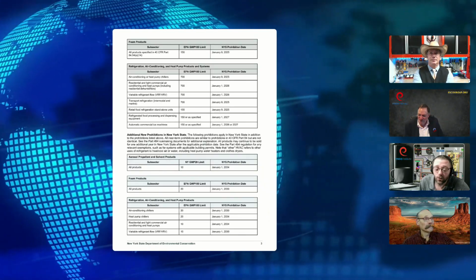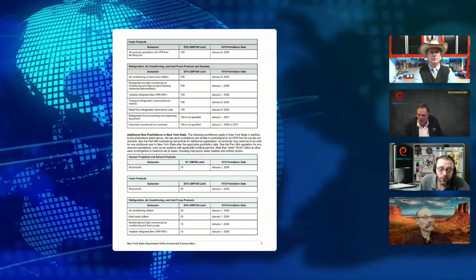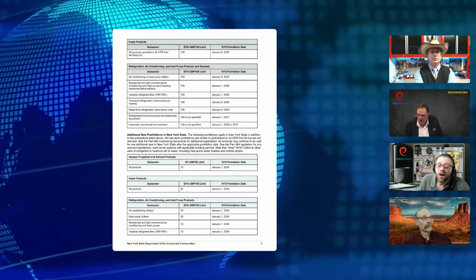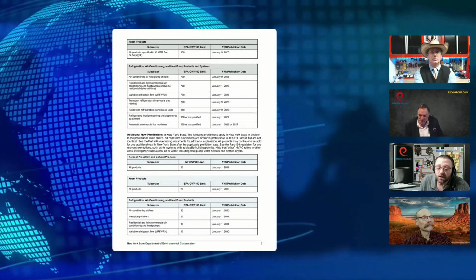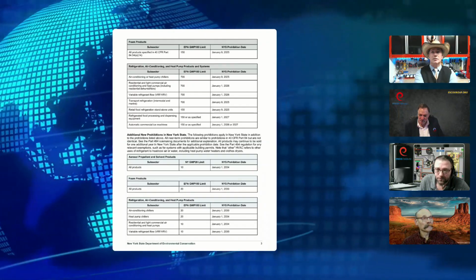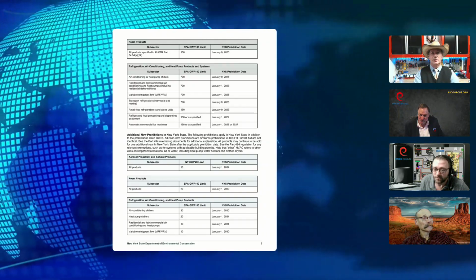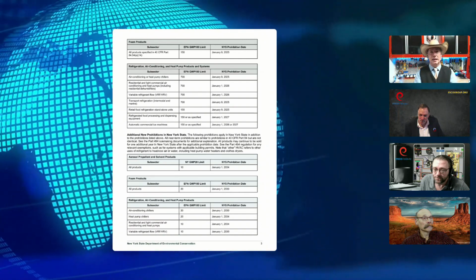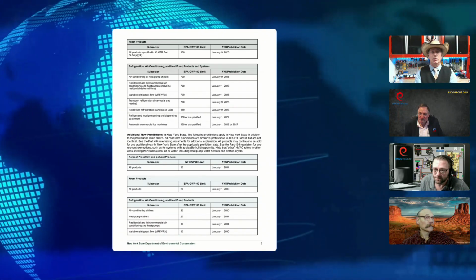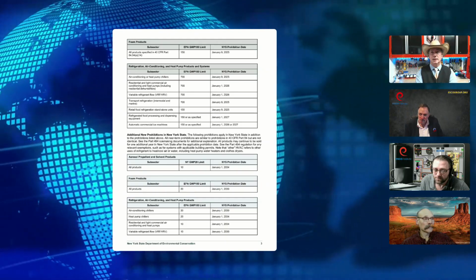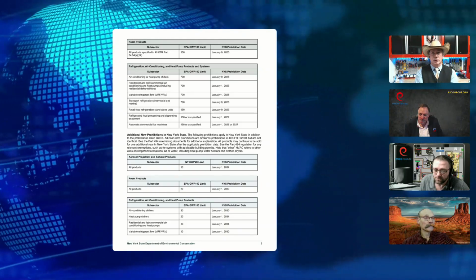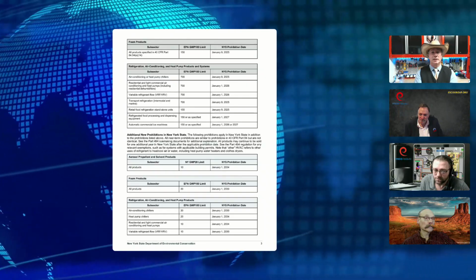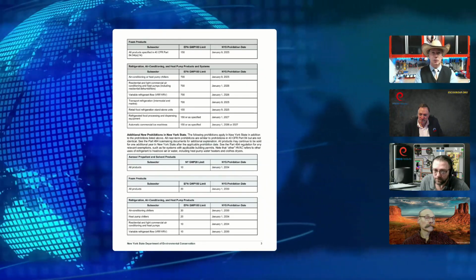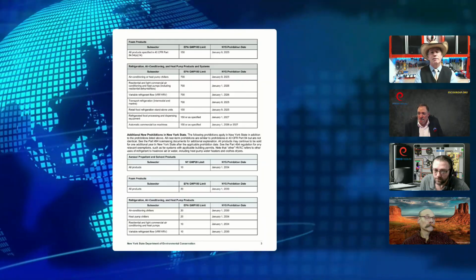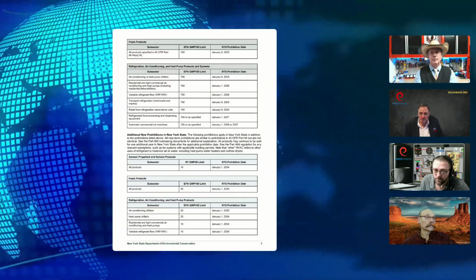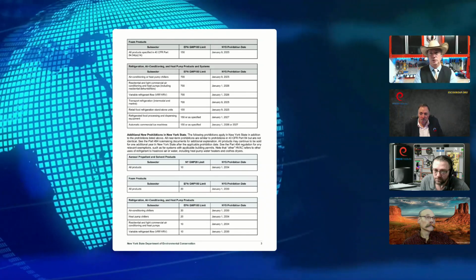There is a lot, yes. Because when you say GWP of 10 or less, you are talking about most of your HFOs, propane, isobutane, ammonia, and CO2. We did a show a while back about where our industry is likely to go, and I'm trying not to use personal opinion, because it's something developed internationally. We actually saw for the very first time at AHR 2024, a year ago, our very first R290 monoblock residential heat pump chiller.